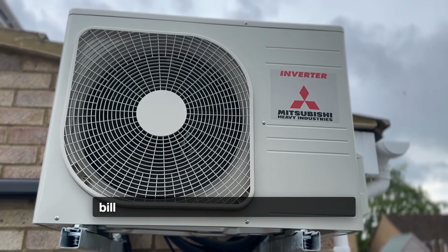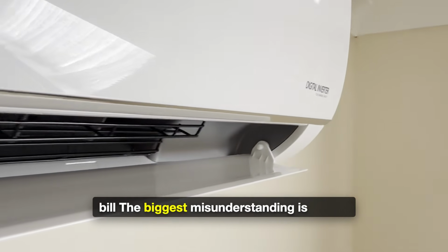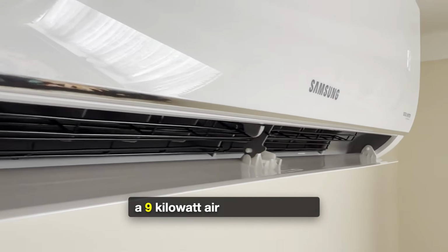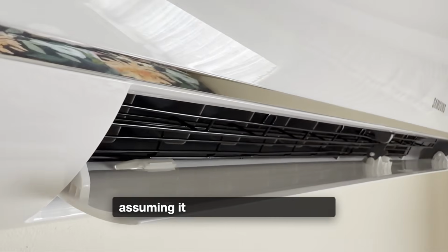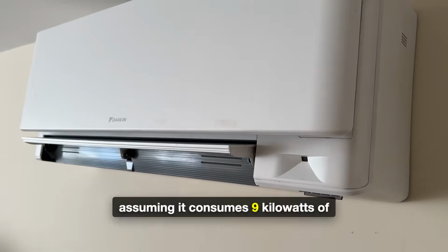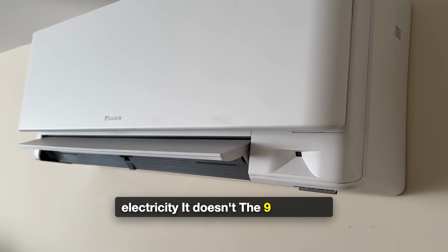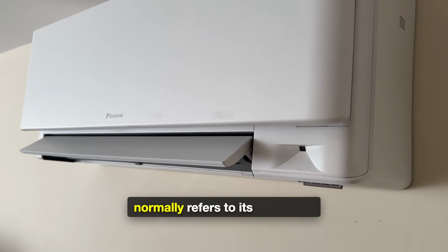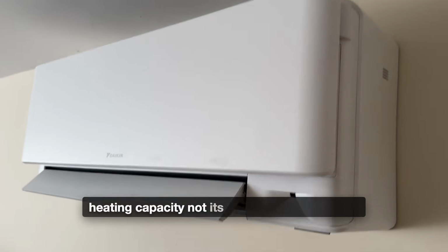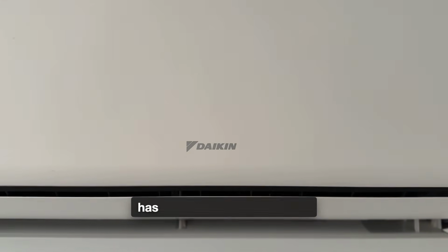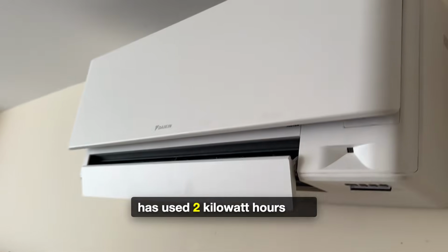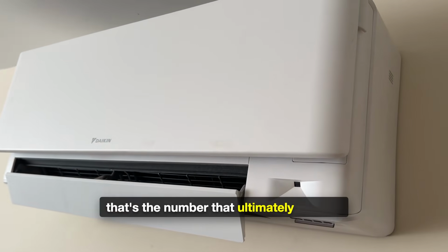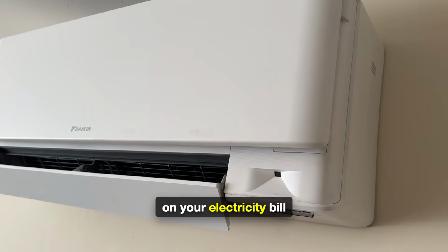your electricity bill. The biggest misunderstanding is seeing a 9 kilowatt air conditioner and assuming it consumes 9 kilowatts of electricity. It doesn't. The 9 kilowatts normally refers to its cooling or heating capacity, not its electrical consumption. If a system draws 2 kilowatts of electricity for 1 hour, it has used 2 kilowatt hours, and that's the number that ultimately matters on your electricity bill.